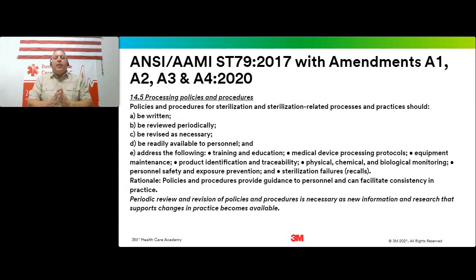Okay, again, we go to the AAMI document in section 14.5. It's giving us guidance, telling us what the policies and procedures should contain. And that's a pretty strong word coming from AAMI. When they say should, there's not a lot of wiggle room there. It's not saying maybe or perhaps. That's a very strong word - one of the strongest words they can use in the document.